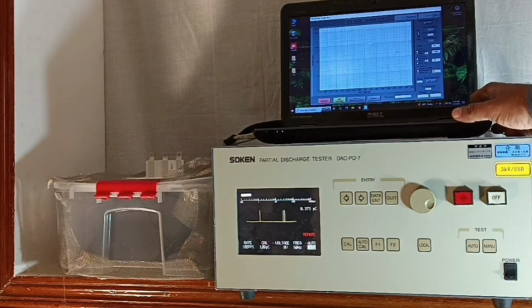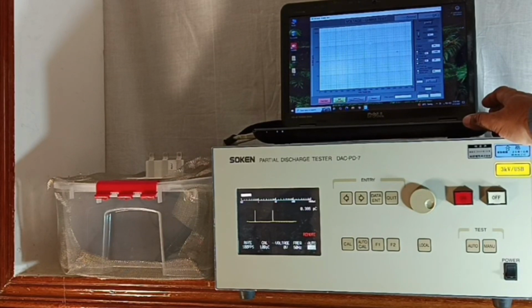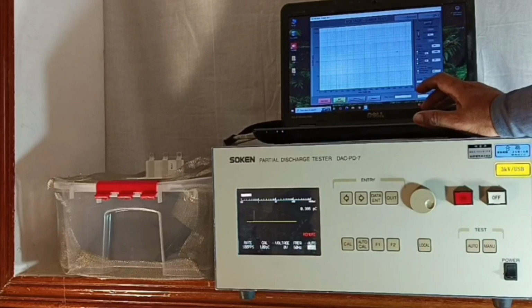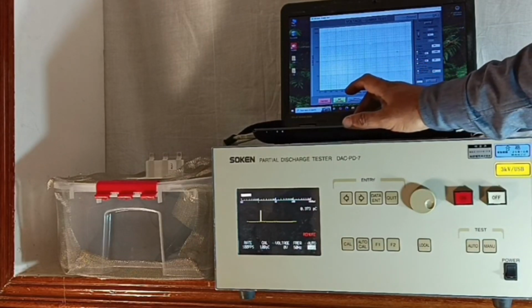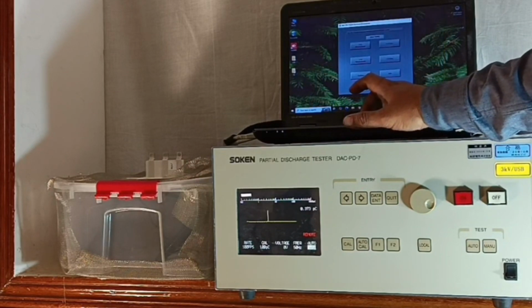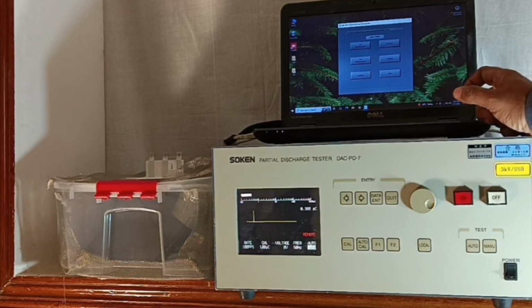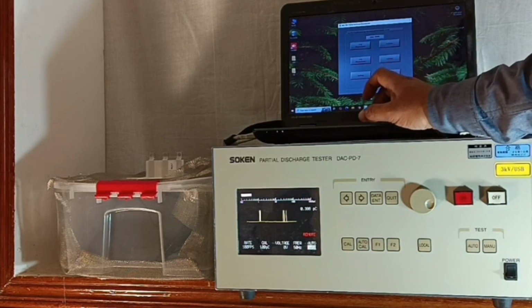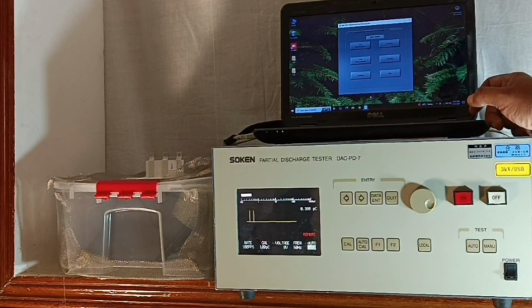The setup is mainly useful for measuring the partial discharge of the twisted enamel wires, the busbar PCBs, and the electronic components, the small motors, etc. When interfaced with the software, you have the VQ measurement, that is voltage versus charges, and the time versus charges, TQ measurement. Both are possible. The minimum measurement of less than 1 pC is possible in this setup.